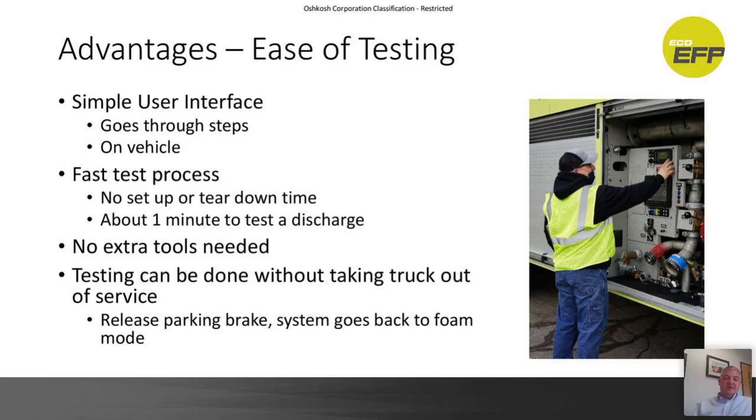And with everything being based on the truck, there's no setup or tear down time. Literally, you can take the rig and pull it out of the fire station, walk up to it and start a test instantaneously. And a minute later, you have a test result for that particular discharge. So it's fast, easy to do. No extra tools needed. There's nothing that you need to hook up and set up with flow meters. Everything is on the truck, so there's no setup time or tools that you need to store.